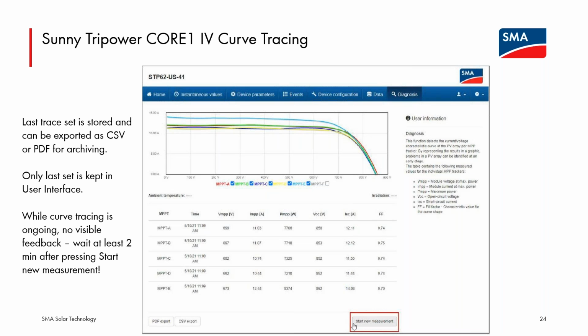This is not the level of accuracy that would allow you to process a module warranty claim, but this could be a first step. If all the strings coming into the CORE1 are the same length, so you expect to see the same VOC, and you see something 30 volts or 60 volts different on one tracking channel, then that's a signal to say, okay, maybe we do need to go shut down the inverter. We know it's tracking channel C. Let's do some actual, high resolution curve traces with a dedicated instrument on the strings coming into tracking channel C and proceed from there. But I think this is a really valuable new kind of diagnostic tool that's built into the firmware of the CORE1 US-41.